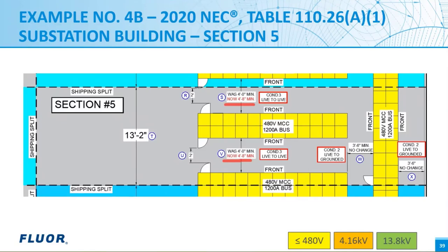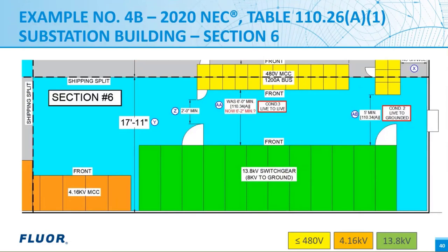If you have an MCC lineup here that is less than 1200 amps and less than 6 feet long, then this new rule won't apply and you can go back to the 4 foot minimum from table 110.26A1. Remember, section six is just to the right of section three that we looked at, and section three was what drove the 17 foot 11 dimension shown near bubble Y. So for this shipping split, it'll be the same.